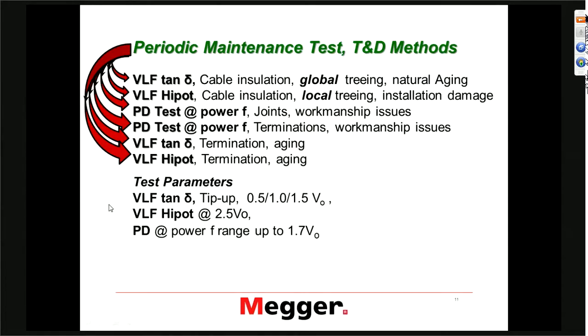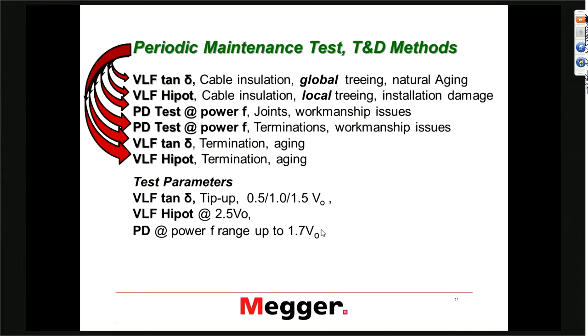The test parameters: for the diagnostic test, the voltage levels are much lower than for the hypot test. The VLF Tan Delta tip-up is typically performed at 0.5, 1.0, and 1.5 U-naught, where the VLF hypot test for maintenance is carried out at about 2.5 U-naught — substantially higher voltage. Partial discharge testing, when carried out at power frequency, typically uses 1.7 U-naught, maybe 2 U-naught; most people do not want to go higher on power frequency PD testing than 2 U-naught.